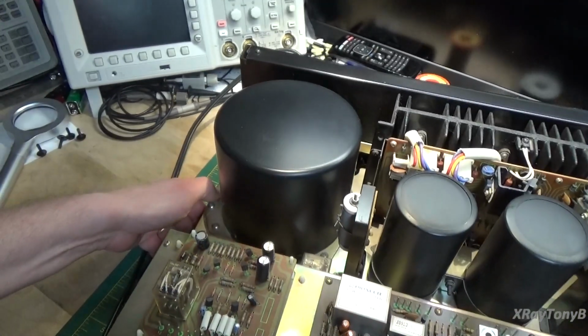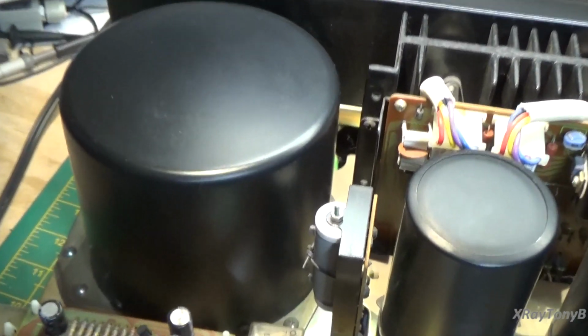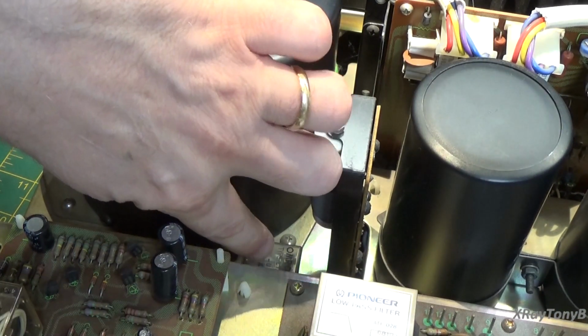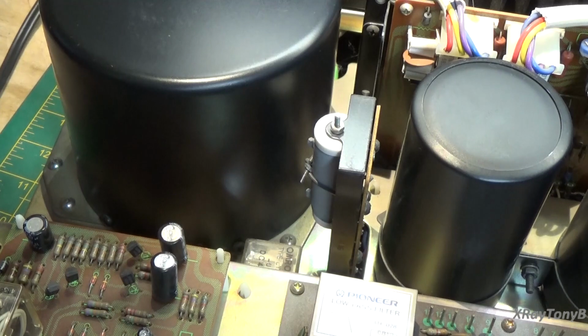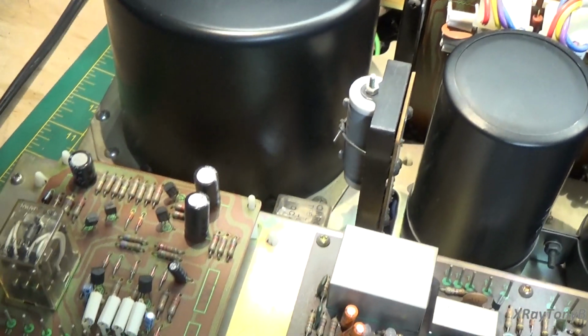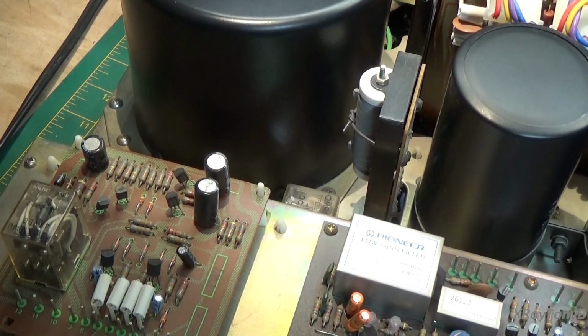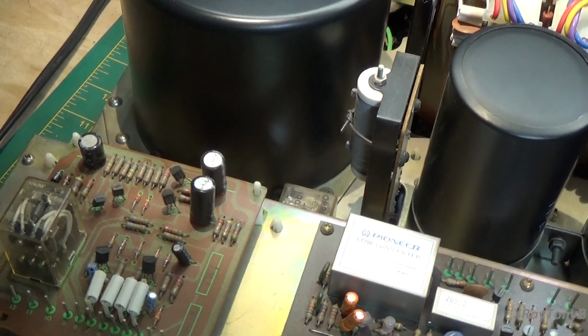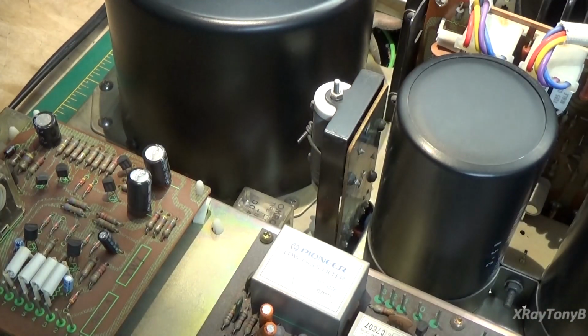And then if you look down here, we should hear this relay kick in, and all it does is shunt out that inrush current limiting resistor and permit the capacitors to complete their charge all the way up to the maximum voltage.